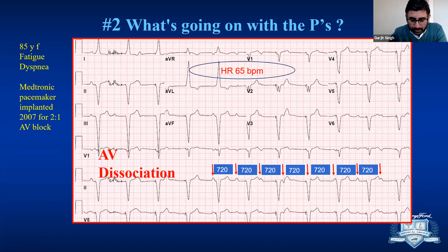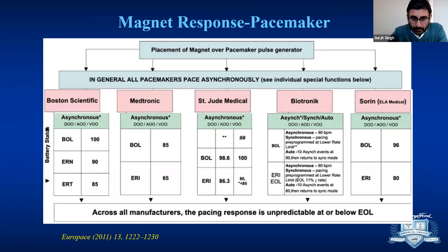So this patient is in AV dissociation because at the end of life, the device goes to a VVI mode. It stops sensing, it stops responding to the atrial channel as well, okay? So this was the ECG before when everything was all fine. So this pacemaker is at end of life. And you should have the slides in your booklet. Basically, when you put a magnet on any pacemaker or device, all the pacemakers will start pacing asynchronously based on the device company. A Boston will pace at 85 beats a minute at end of life, a Medtronic at 65, and so on. Alrighty, going to the next ECG, what is the atrial lead sensing?